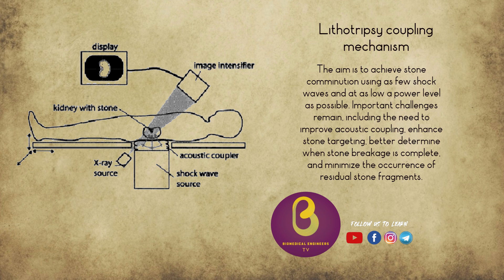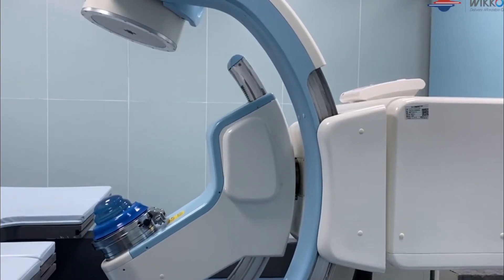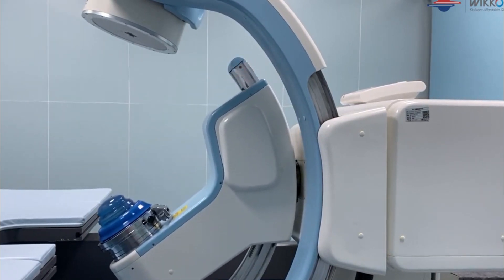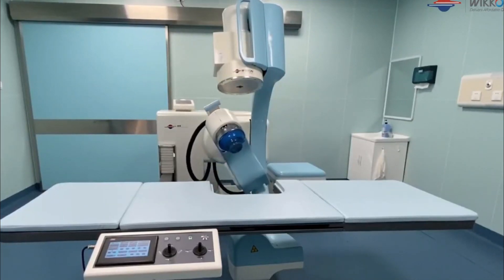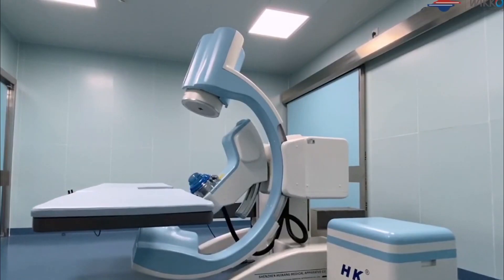In first generation lithotripters like the Dornier HM3, the patient was placed in a water bath. With second and third generation lithotripters, small water-filled drums or cushions with a silicone membrane are used instead of large water baths to provide air-free contact with the patient's skin. This innovation facilitates treatment of calculi in the kidney or ureter, often with less anesthesia than required with first generation devices.